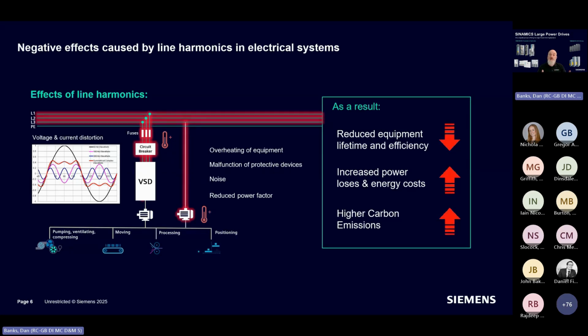That current circulates to your circuit. So as you can see in this diagram here, once you've got that distorted current circulating, it's not doing any work, may not be costing you any money if you're not measuring it, but it's absolutely heating up your circuit breakers, your fuses, your cabling, your transformer, and potentially any other devices on the network. For example, there's an electric motor here that you can see that'll be generating extra heat. It might also be generating noise. It could be causing you nuisance trips with any thermal devices because of this extra heat, and it's messing with your true power factor. So those are the challenges that we really see in industry in the UK in relation to harmonics.